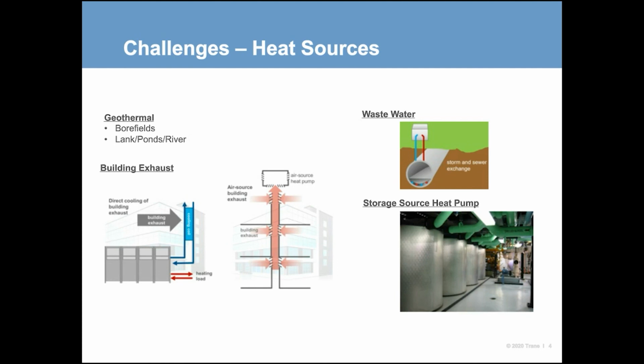The second one on the right there, that's a really interesting one that we saw in Canada. They actually had a row or a bank of air to water heat pumps, and they were in a penthouse. And the building took all the building exhaust and routed it up into that penthouse, like underneath it. So it might be minus 20 degrees ambient outside in Canada during the winter, but that penthouse is at 75 degrees. All right, that's an awesome spot to run a heat pump in heating mode. So that was a cool application. Top right, wastewater. We're seeing more people try to use this, either the building's wastewater itself or tying into like a district storm or sewer drain and pulling BTUs out of that wastewater.